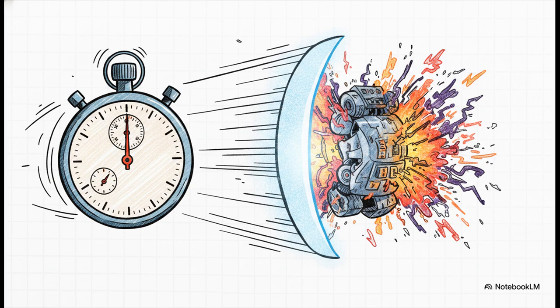It really just comes down to the physics. Damage energy is proportional to the square of the current multiplied by time. So the thermal and mechanical stress compounds every single cycle that fault stays active. Just a tiny delay in clearing it causes a massive, disproportionate amount of damage to the windings. You have to clear this event in milliseconds, not minutes, not seconds, milliseconds.